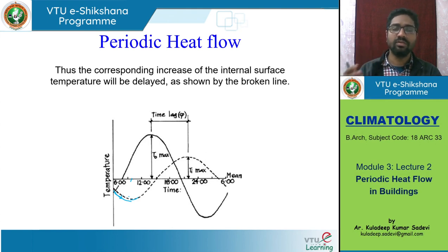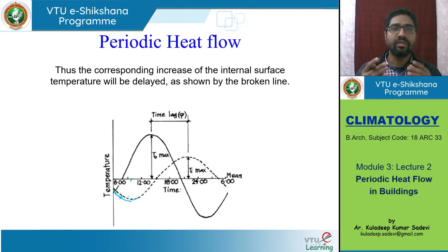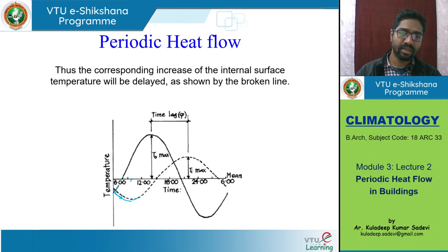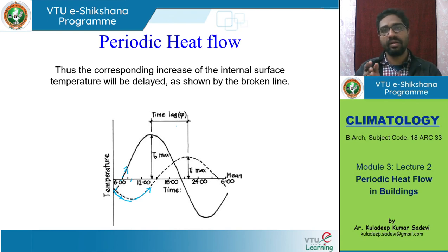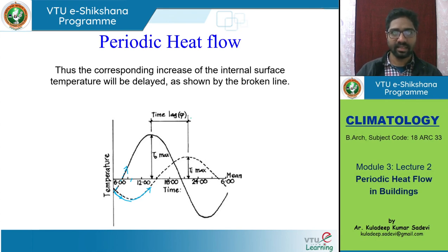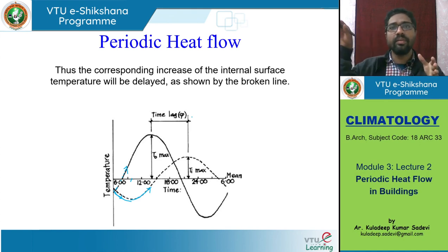If windows are closed, curtains are closed, and heat is not entering the building directly, then through conduction through the walls it will take time for the wall to transfer outdoor heat indoors. Whatever heat gain is happening at the outdoor wall surface — that rise in temperatures will start being visible indoors only after a certain time. This corresponding increase in the internal surface temperature will be delayed compared to how it is happening at the outdoor surface. Heat gain is delayed, and heat keeps coming inside until outdoor temperatures start falling down.